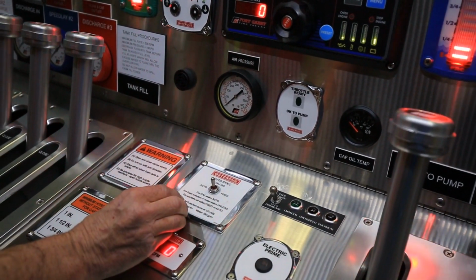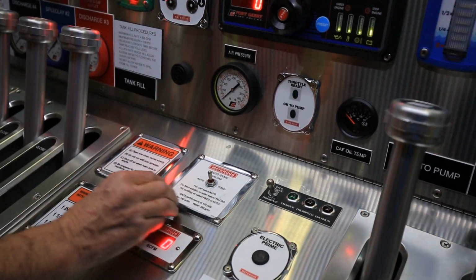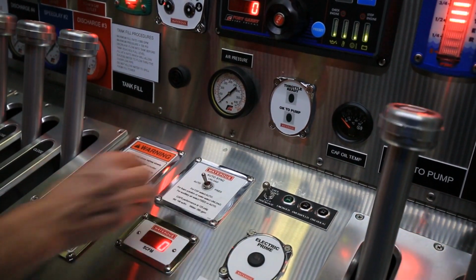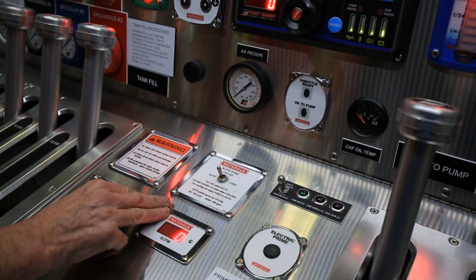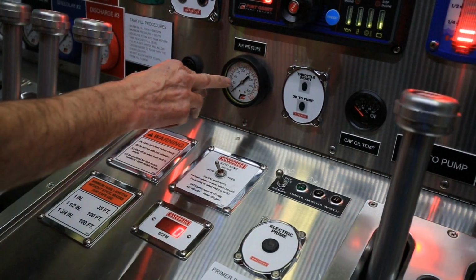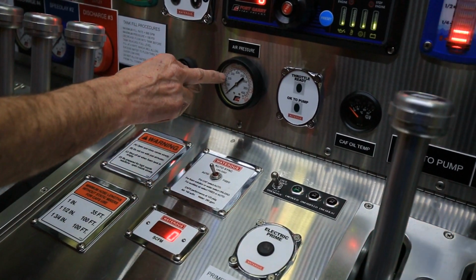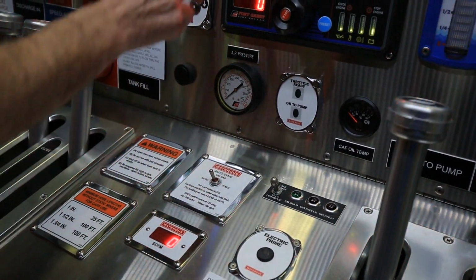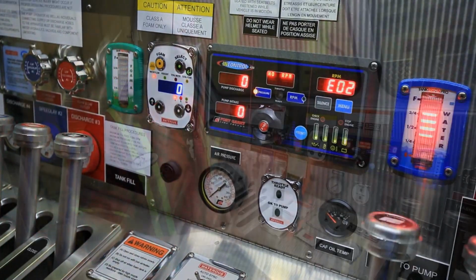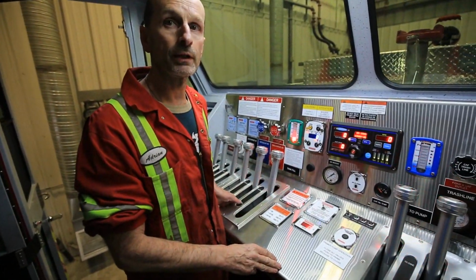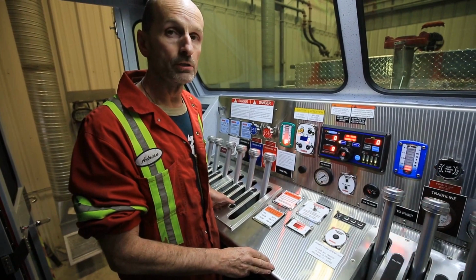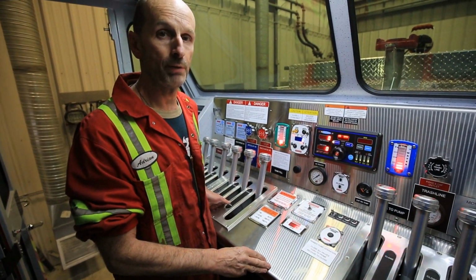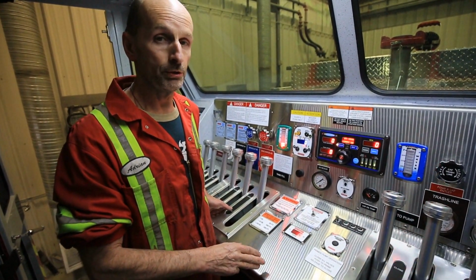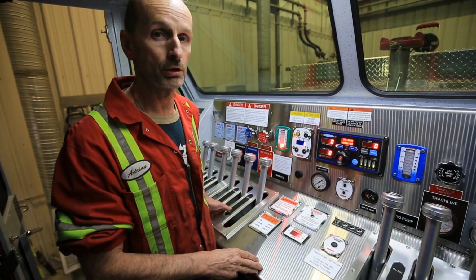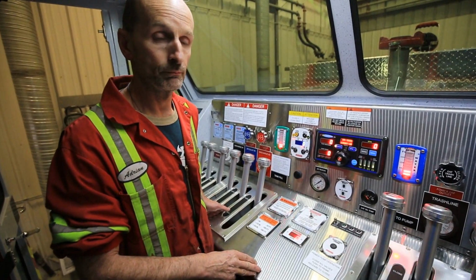If using the CAF's compressor to make CAF foam, the switch will be put in the auto position, and in this case the air pressure on the gauge will follow closely to the actual pump discharge pressure on your water pump. One thing to note with the CAF system, the oil is cooled by water from the pump. The CAF system shouldn't be used unless the water pump is pumping water.